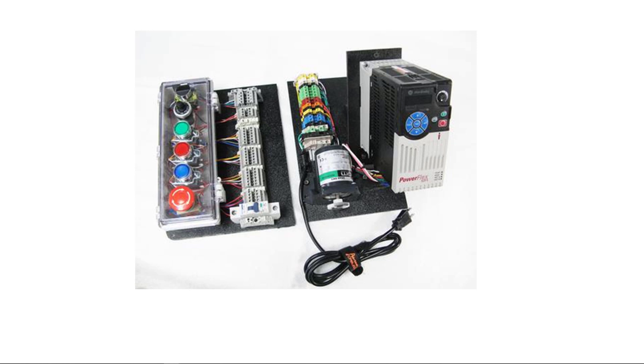Now if you know anything about variable frequency drives, the first thing they do is convert the AC into DC. They fully rectify it and then they charge up large capacitors and that's the bus, that's the power bus. That's the voltage in power that they have to work with, that's in the reservoir, the capacitor.